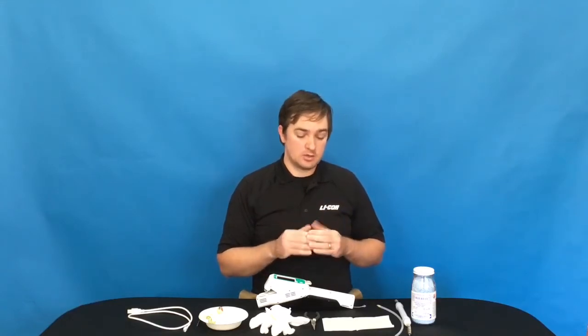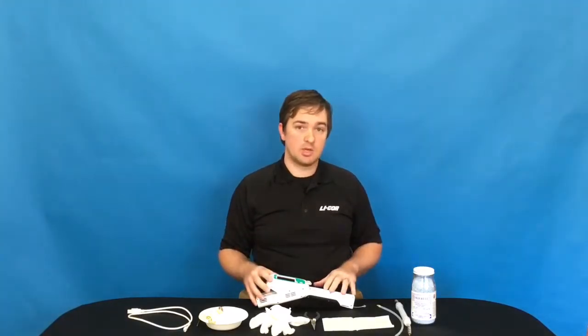We don't recommend using silica gel because it doesn't entirely get all the way down to 0. But Drierite or similar desiccants will get you to that completely dry airstream. So with all of these things in place, we will start to take apart the instrument and remove those buffer beads.